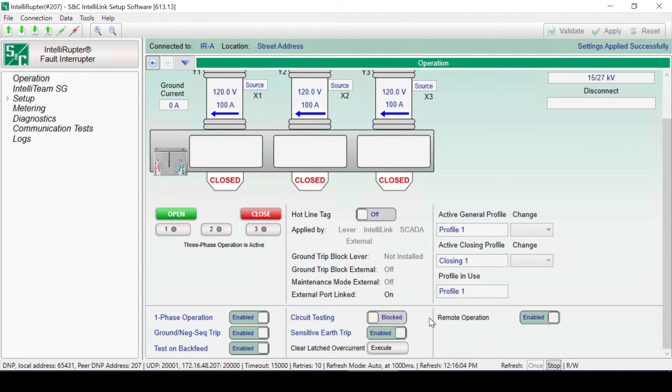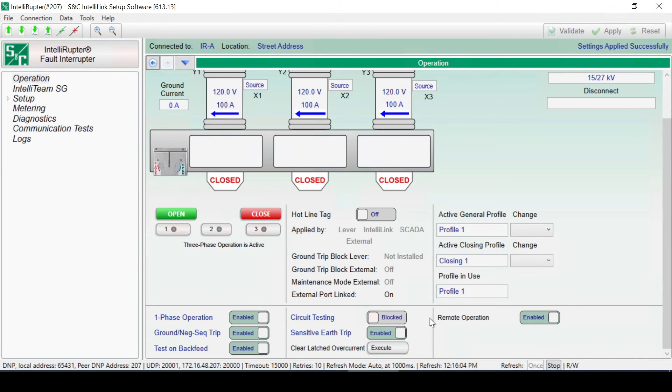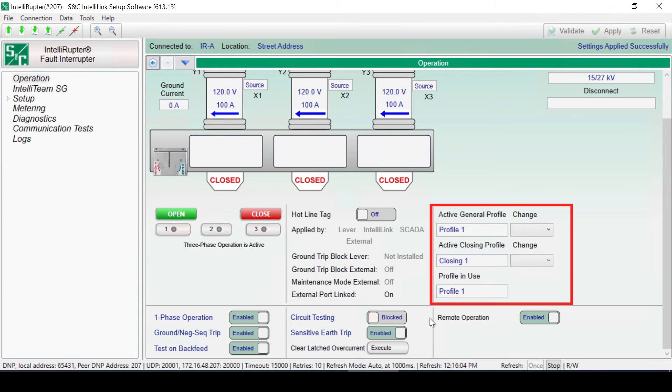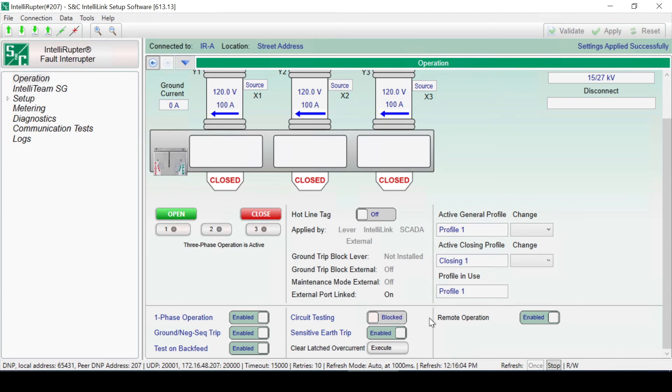Protection profiles contain settings that define the protection functionality for the fault interrupter. Only one profile will be in use at any point in time. In the final section of the Operation screen, three profile fields are displayed: the Active General Profile, Active Closing Profile, and the Profile in Use. Profile in Use will change when other features are in use, such as Hotline Tag.